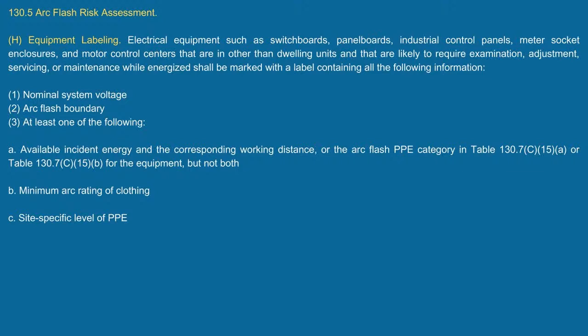Or it says I can use what? The arc flash PPE category, that is in 130.7C15A or B for the equipment, but not both. Or I can have the minimum arc rating of the clothing or the site-specific level of PPE. You got to have one of those following. Now, is there anything else you might want to put on that label that's not listed? Because you can always go above and beyond that. Well, I may look at this. I would put where all these devices are located in the property, so you know where to go to actually isolate this to make it an electrically safe work condition.